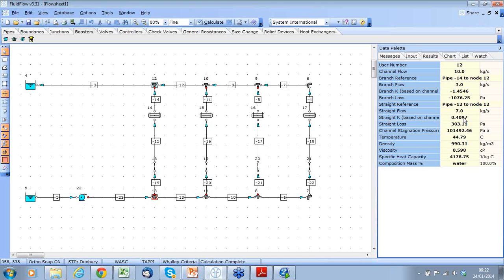But there's further information in the help file on that and what is an acceptable K value for idel'chik Ts and Miller Ts and so on. And often you'll come across this warning when we have a T-junction with different sized T connections. So you might have a 2-inch pipe connection and the remaining 2 connections on the T might be 4-inch. So the software extrapolates the equations to determine the K value accurately. Okay, and all experimental data to date is based on equal sized pipe connections, hence the warning messages.